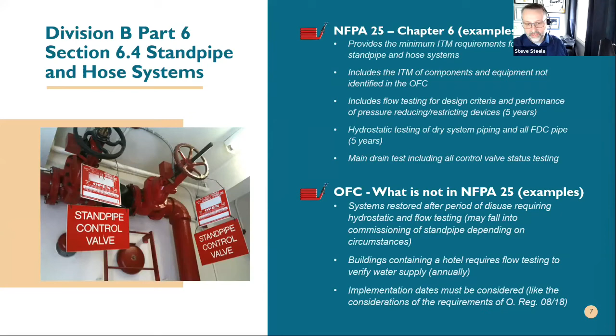Again, giving the bare minimum requirements hits a lot, especially with sprinkler systems—they're getting more complex, with a lot of bells and whistles. Going through some of this, small things like relief valves become very important. Believe it or not, NFPA 25 does not recognize relief valves, whether that's a gap. I know that information has been passed on, or they're looking at it, but to ensure these relief valves work—it doesn't necessarily affect performance, but it does possibly affect the integrity of these systems as well.